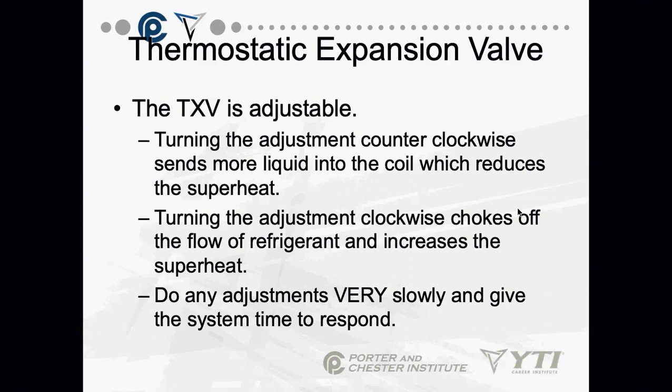TXV is adjustable. I need you to memorize this. I hate telling you guys to memorize things, but this slide is important. Turning the adjustment counterclockwise sends more liquid into the coil, which reduces the superheat.